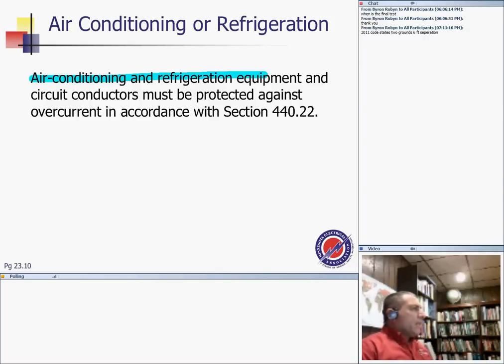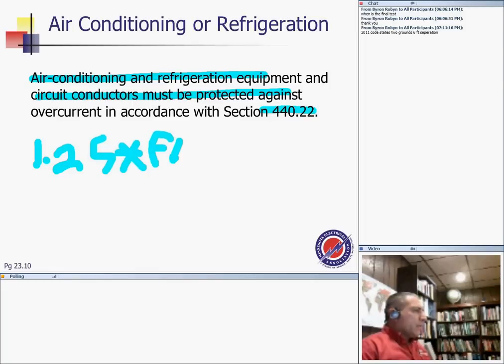And guys, we have an air conditioning. When we protect it against overcurrent according to 440.22, which basically tells you 1.25 times the full rate of the equipment, full load current, and that's how you size the conductors.